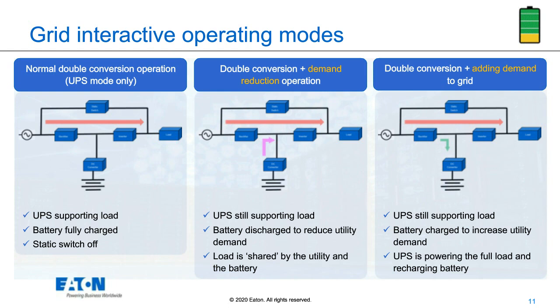This incoming red arrow is still the same - we're still converting AC to DC and DC back to AC - but the battery is involved now. We're not hitting the battery with a super fast, steep discharge rate. Think of it more as skimming the energy off the battery slowly, under a controlled situation, with the battery basically helping to support that critical load.